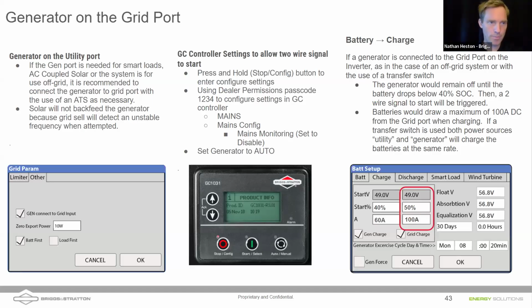As well, you're going to tell the inverter that you've got a generator on the utility port, the grid port, and then we can set up our charging rate there. And one thing to keep in mind about your charging rate is when you're charging off a generator, when you're running a generator, the generator has two jobs. One job is to cover the loads of the inverter, because the inverter is not producing power from the batteries now, it's charging the batteries.